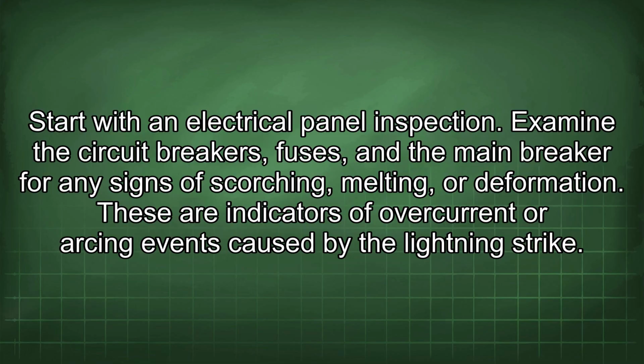Start with an electrical panel inspection. Examine the circuit breakers, fuses, and the main breaker for any signs of scorching, melting, or deformation. These are indicators of overcurrent or arcing events caused by the lightning strike.